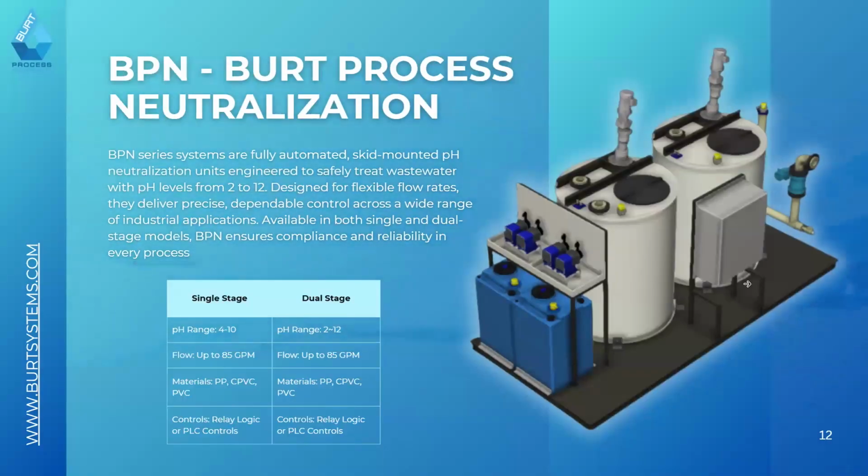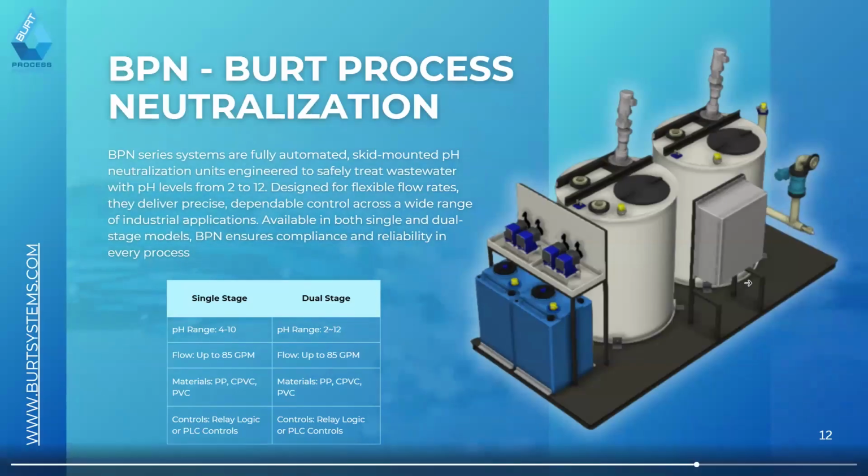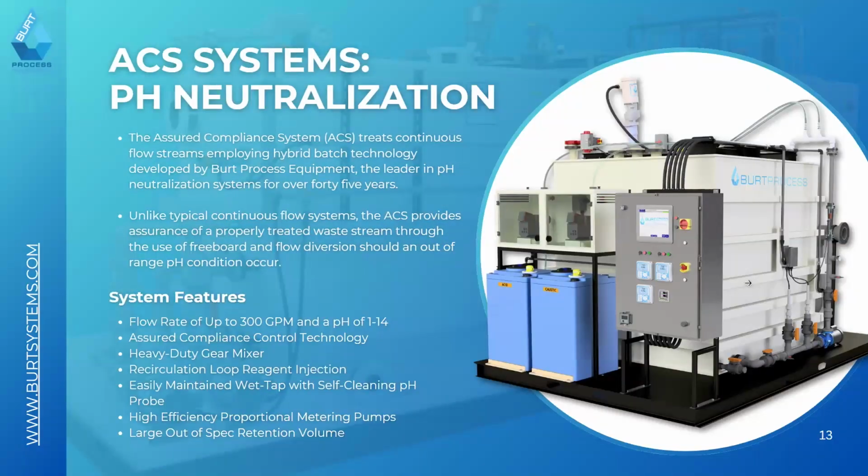This is what you would more typically see, a traditional two-stage configuration. Again, it lacks some of the more sophisticated control processes that go along with the system, such as recirculation and redundancies. It does offer that redundant tank design, which can be utilized to meet that CSTR modeling. This is the more common one, and we classify it as an ACS, a broad categorization that you'd see typically in the pharmaceutical industry. It's a system that has built-in batch capabilities. So this is a fully automated system.